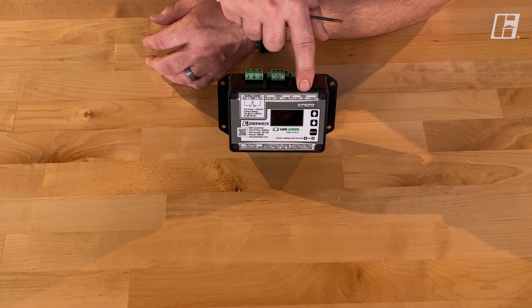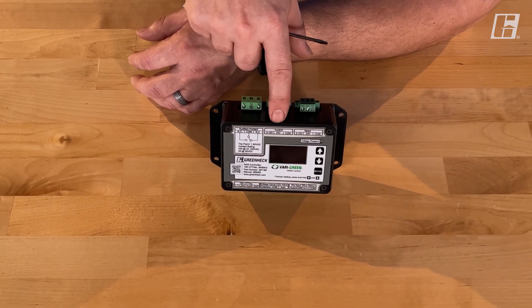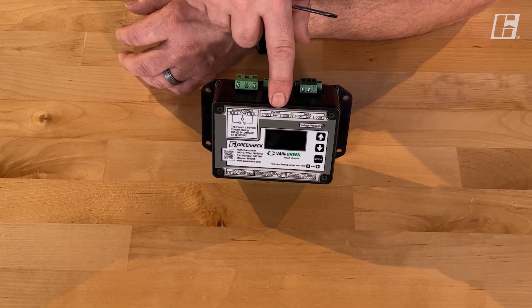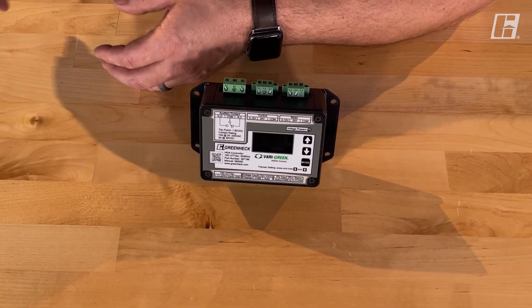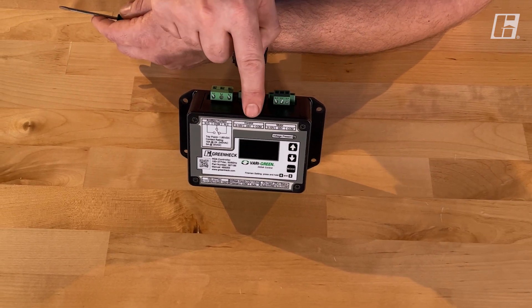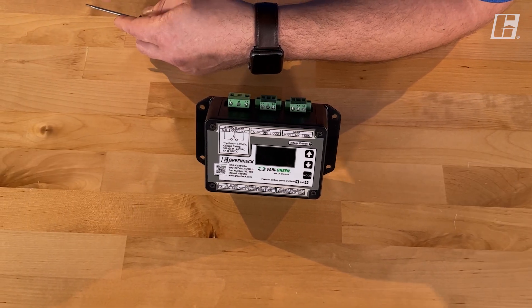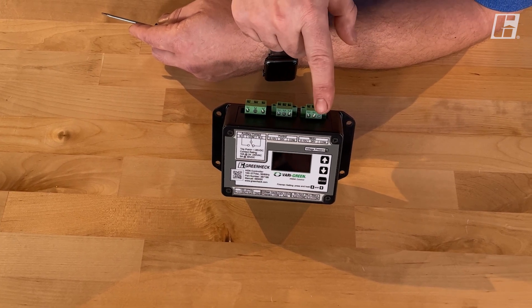You'll typically not see a wire used on that 24-volt terminal. Our next terminal set is labeled control. This again has common, 24, and zero-to-ten. The 24-volt terminal is a 24-volt DC output meant to power other controls like a Vari-Green constant pressure controller or a Vari-Green remote dial. Common and the zero-to-ten volt is an input — we're taking another control's speed reference, bringing it into the HOA, and when appropriate it passes it out to the motor.